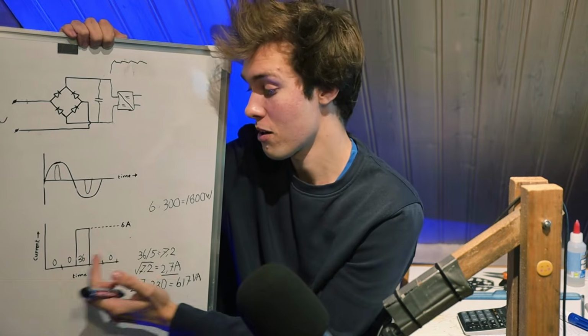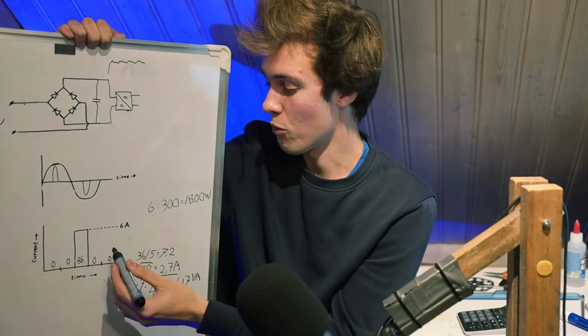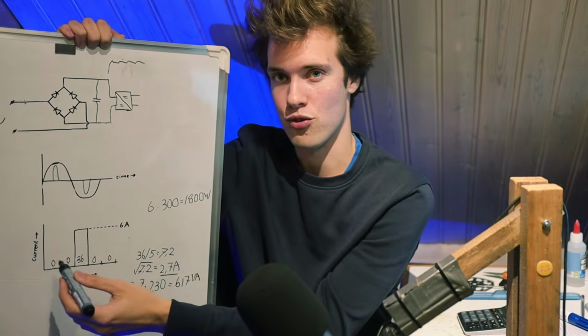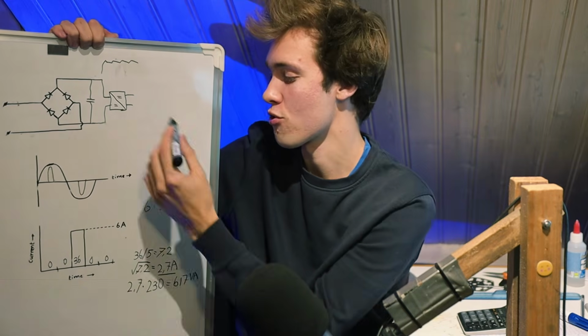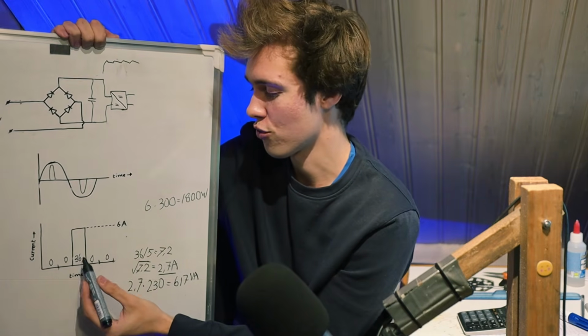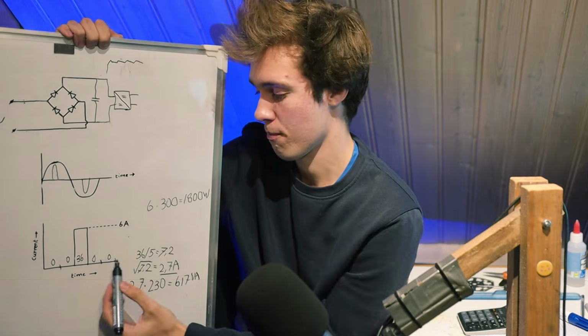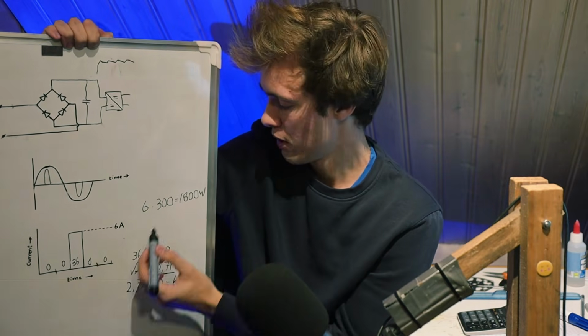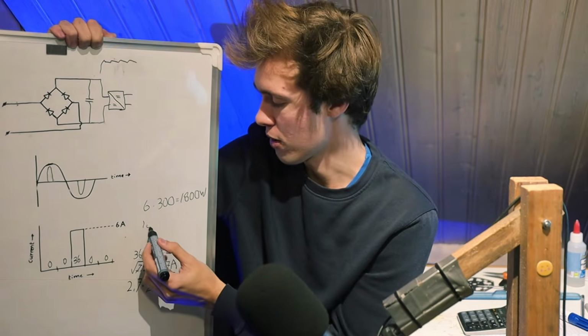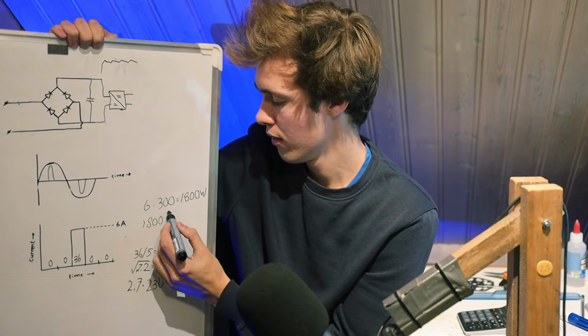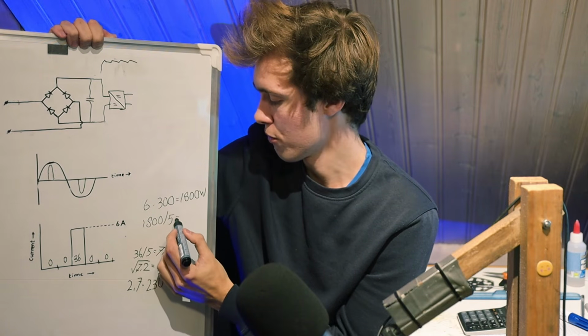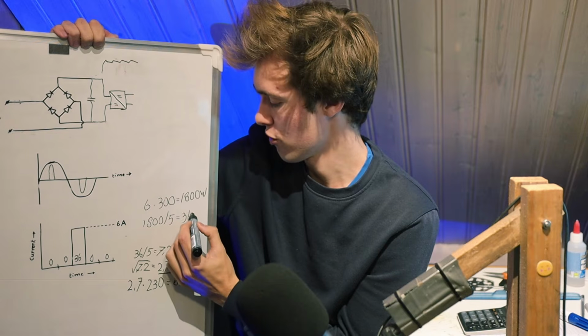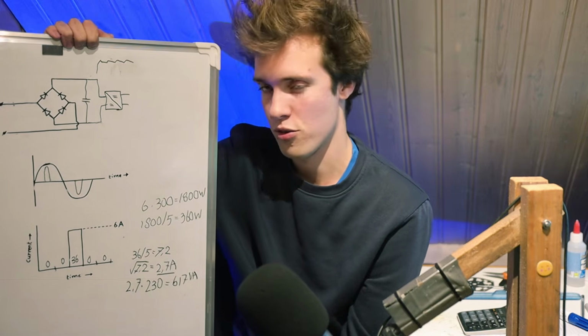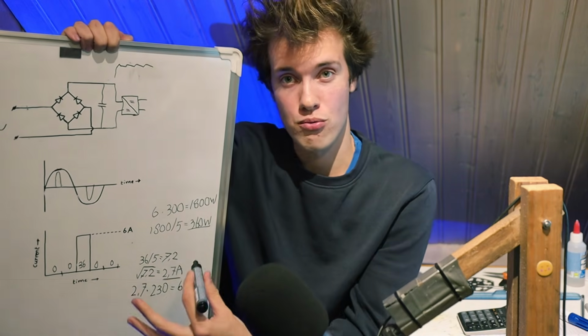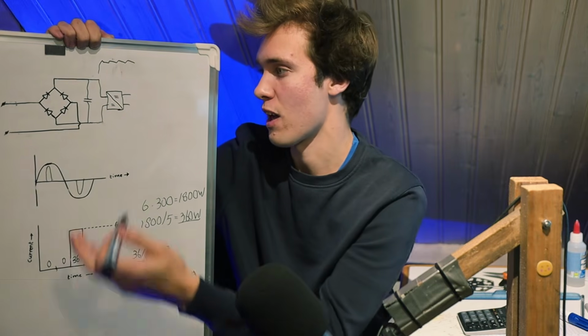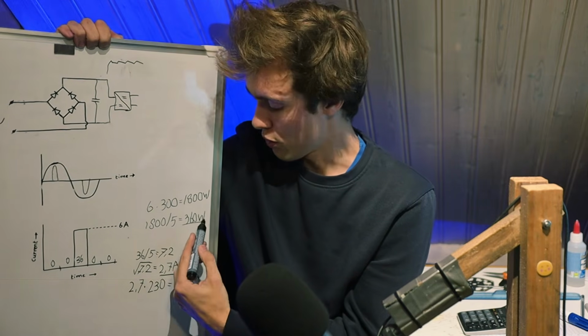The majority of the time there is no power, it's zero. So to get the average power consumption, the actual power consumption of our system, we simply take that number and divide by 5, because we have 5 chunks here. So 1800 divided by 5 gives us 360 watts. That is the actual real power consumption, quite a bit less than 617 volt amps.